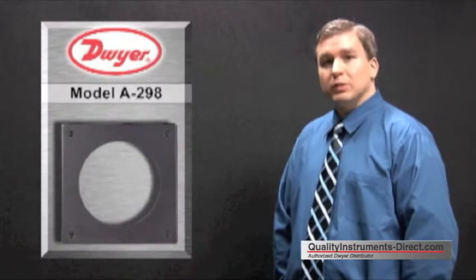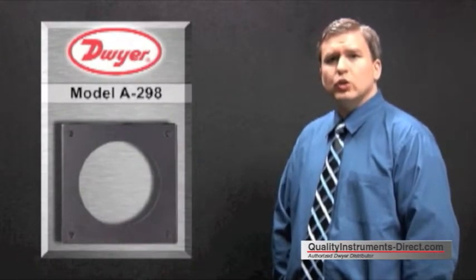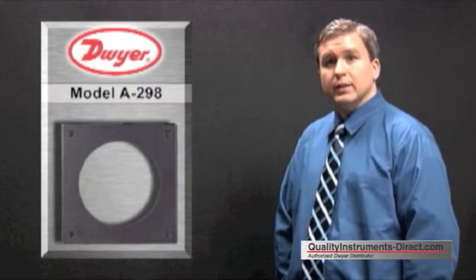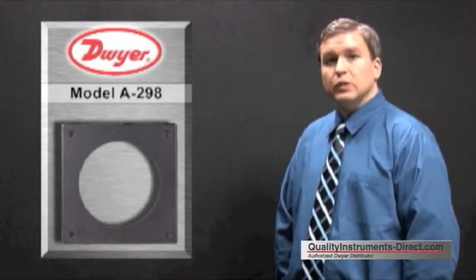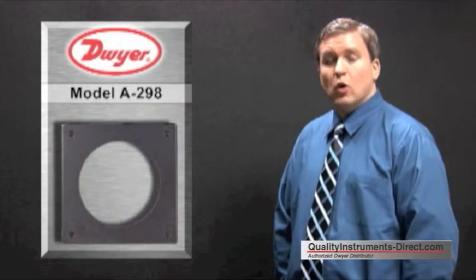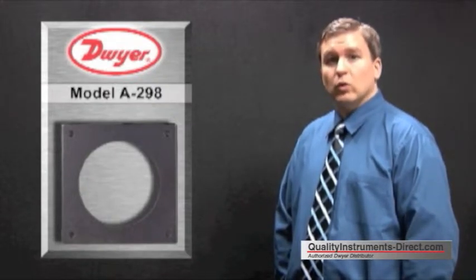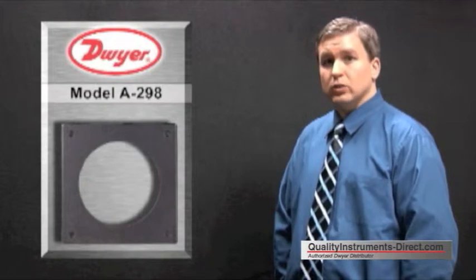For high pressure or medium pressure applications, use the A-298 for flush mounting. In those applications, make sure that there is at least a 4 and 3/4 inch or 120 millimeter hole in order for the Magnehelic to slide through.